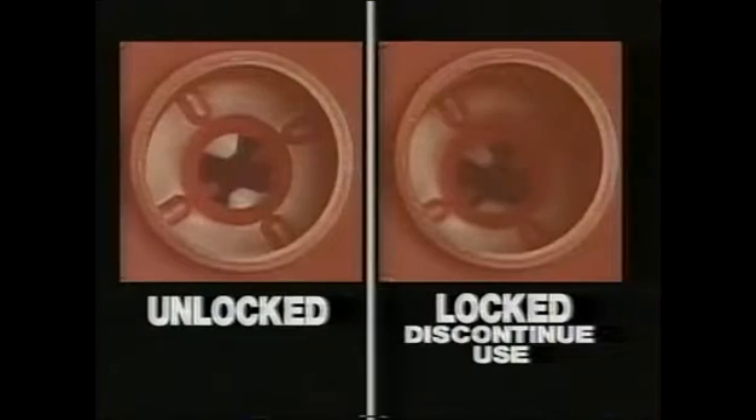The automatic zone houses the mechanical apparatus that automatically unwinds the used blood collection needle from the holder. When the container is filled, the mechanism locks in the down position and will not automatically unwind additional needles. The neutral zone serves a very significant dual function: first, it creates a safety area between the mechanism and the actual needle collection area.